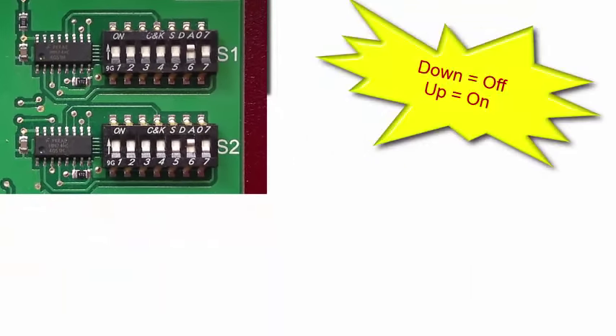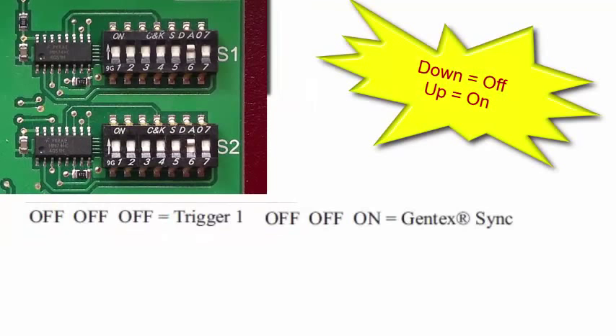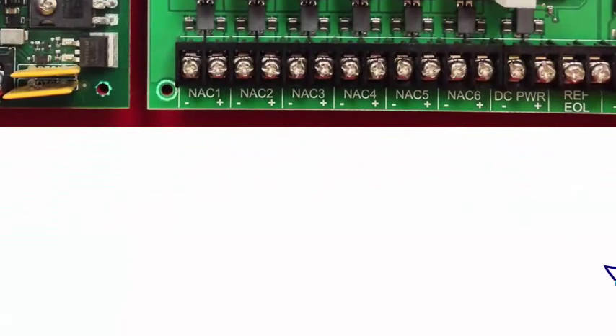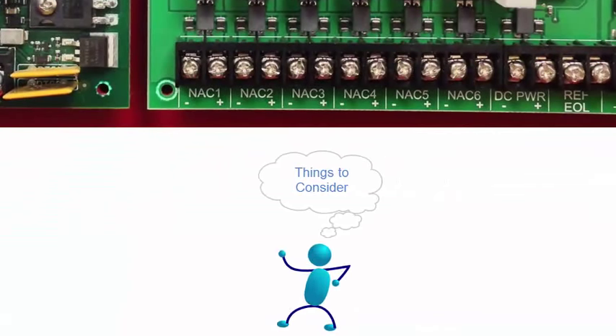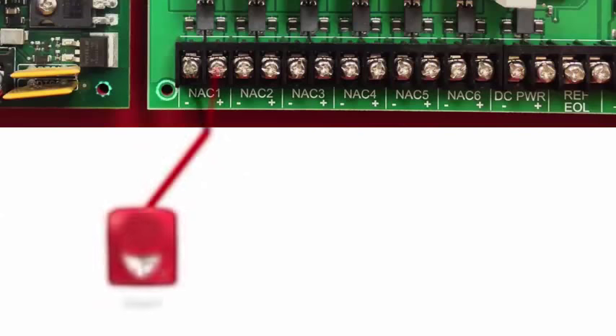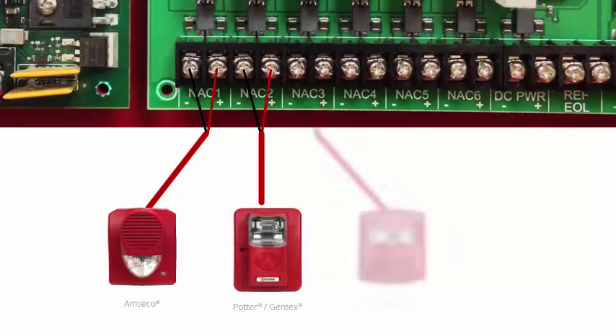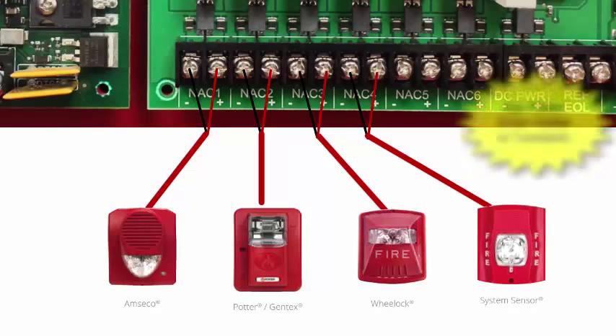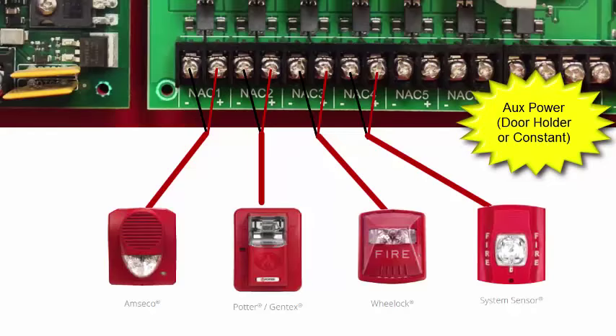As you can see here, these two notification circuits for NAC 1 and NAC 2 are set up to be triggered by input 1 and to be Gentex sync. Some things to consider when programming the PSN power supply notification outputs. Each circuit can be programmed individually. So you could have one circuit of AMSECO, one circuit of Gentex, one circuit of Wheelock, and one circuit of system sensor. And all your strobes would synchronize. That's called quadrasync. In addition to that, any of those circuits could be DC power circuits which can be door holder or constant power.